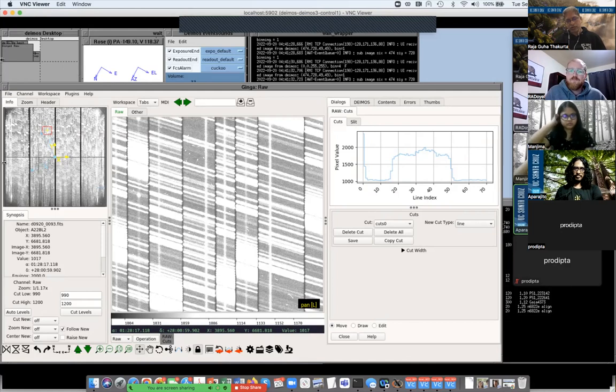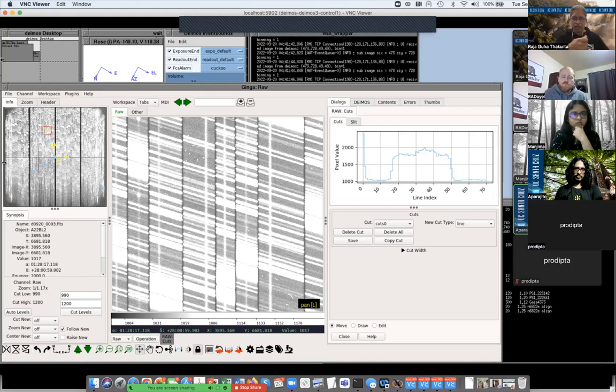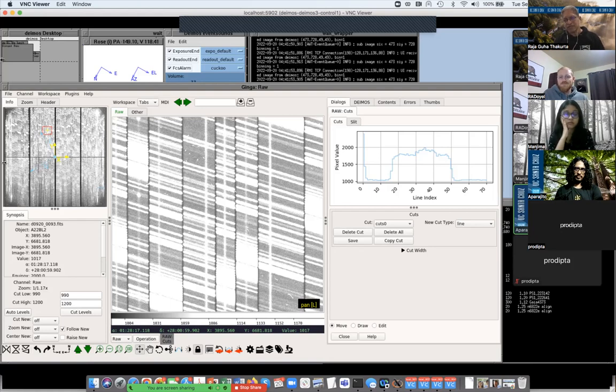Now, the thing that can cause it to drift is there's a physical gap between the metal plate through which light is coming, then it's hitting a collimator mirror, going through filters, hitting a diffraction grating, ultimately going through a camera, landing on a CCD. There's physical space, about the size of this room, actually. I've sat inside DEIMOS while it was being constructed. You were given little tours where you can climb into it. It's like climbing into a space module, I imagine. Anyway, it's big because it's going on a big telescope, a 10-meter telescope, everything scales.